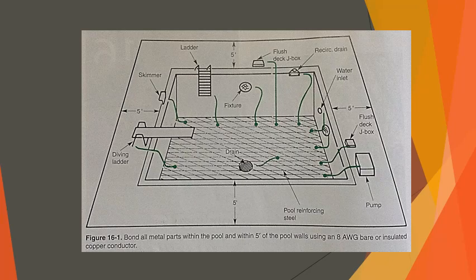Installation of electrical wiring in and around swimming pools, indoor and outdoor, is of much concern to the NEC. The requirements for such installations provide rules that will ensure safety. Bonding. The specific installation requirements for swimming pool wiring methods are found in Article 680 of the Code. Due to the presence of water, the possible pathways of electrical currents must be strictly controlled. Any stray currents, those currents that do not follow the intended path, moving between metal parts in and around the pool can be extremely dangerous.